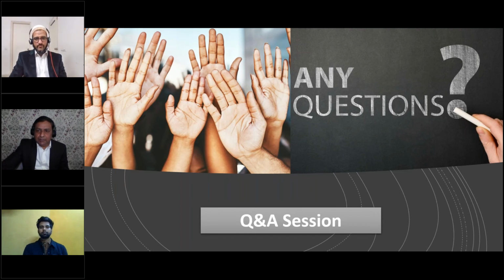Absolutely. I have a related question from Eric Enstead. He is asking what is the standard we need to follow if we are developing a software product. Is it okay if I answer that question, Salman? Yeah, sure, please go ahead. Eric, you will have to follow IEC 62304, software development lifecycle management, for software development.